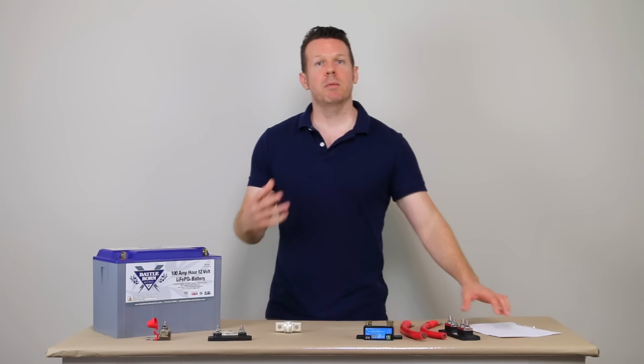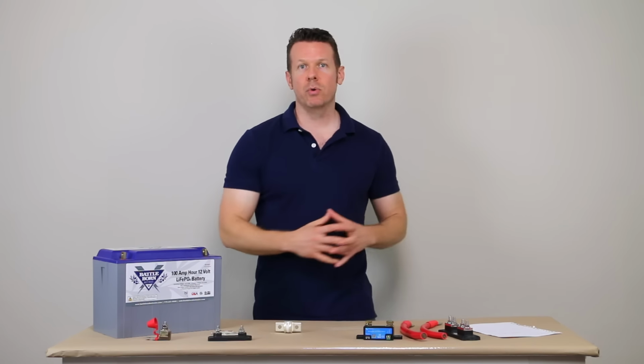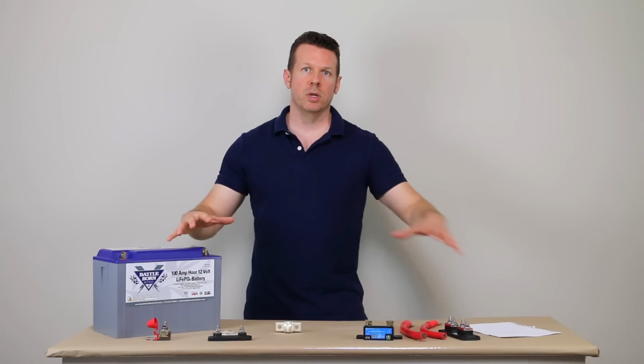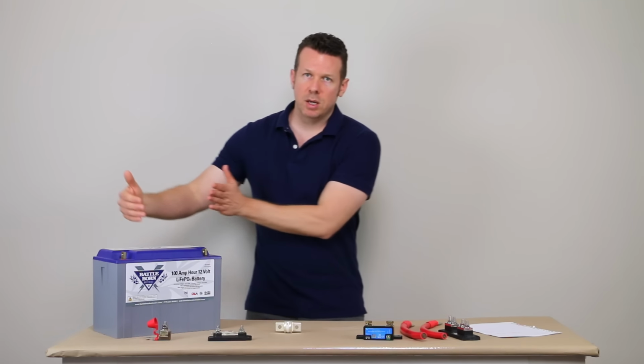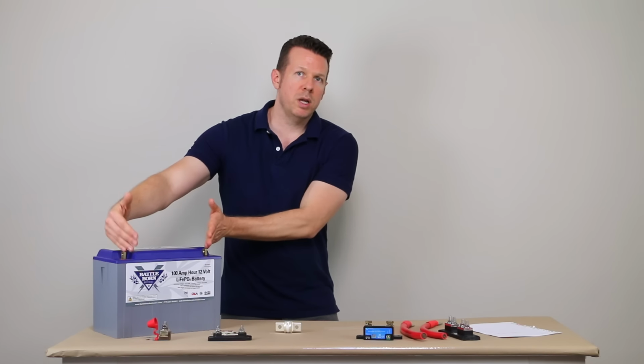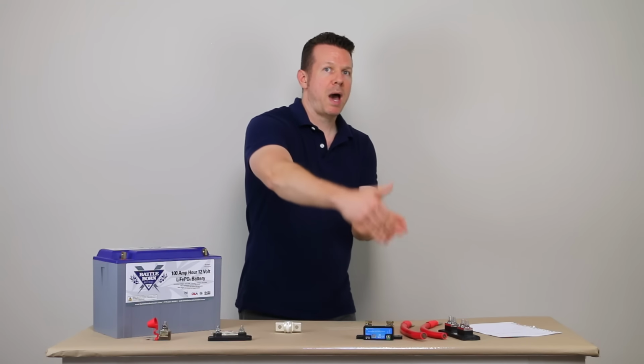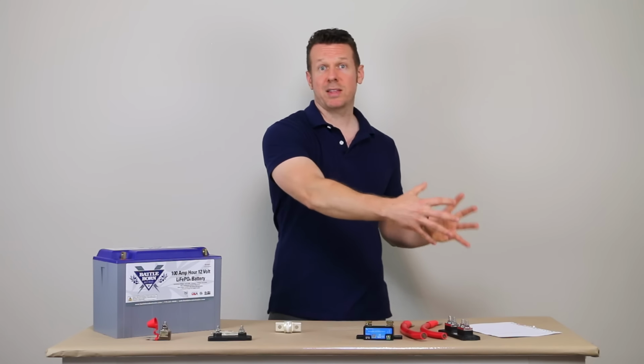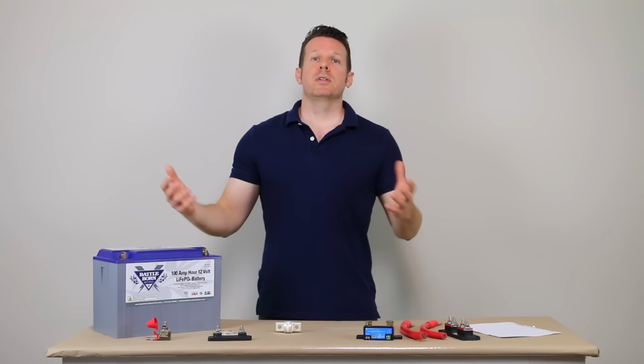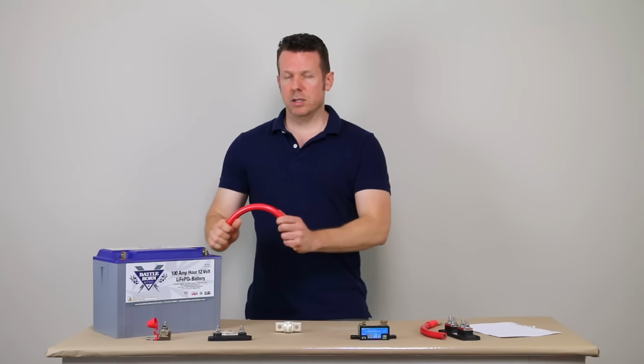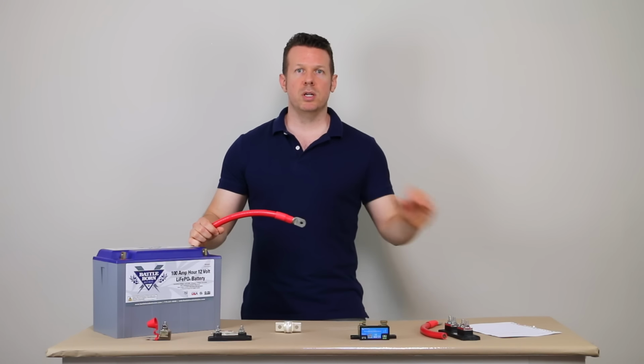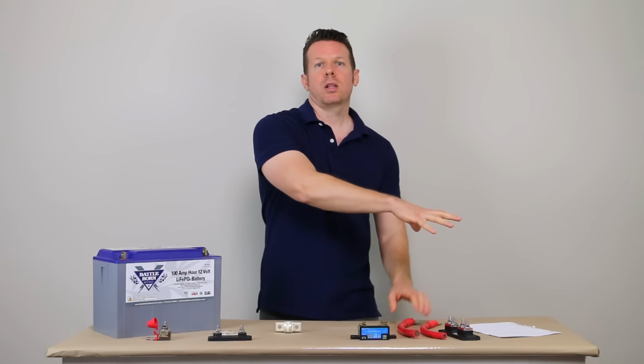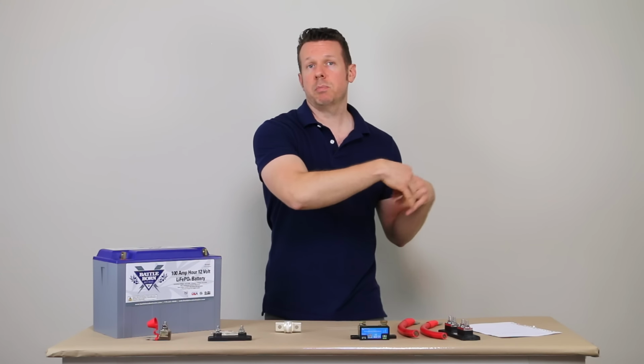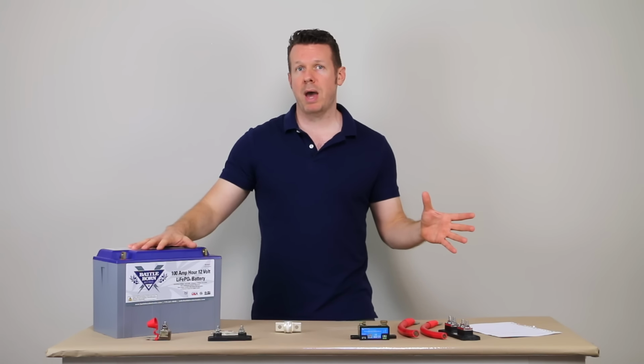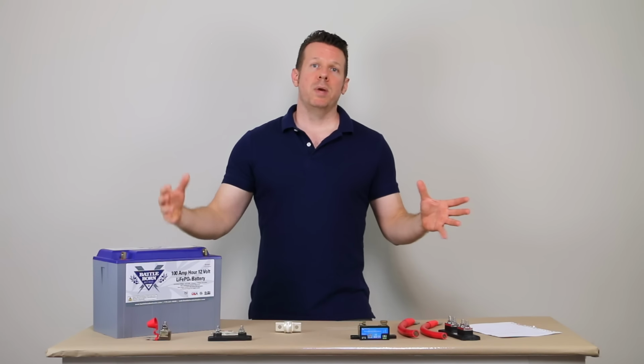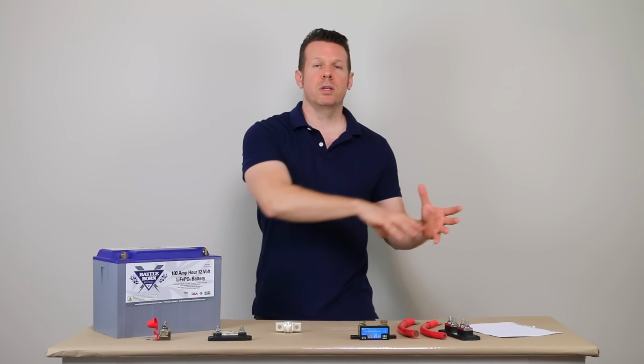Mistake number 3, having a battery that's at the end of the line. With battery banks, we usually have multiples, and it's tempting to bring in positive and negative on one end and just link all the batteries, and in that case you would have a battery that's at the end of the line. Because each link is like a little resistor, there's a voltage drop over each link. Once you get to the end of the line, that battery is going to be charged, and also discharged, less than the battery that's at the front of the line, and to some degree the batteries that are in the middle.